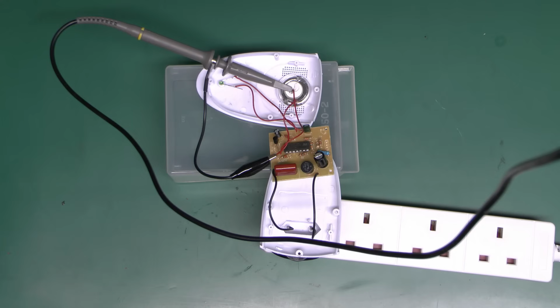Now here's the dubious test arrangement. So mains voltage is in here, circuit board there, and then I've got the probe here connected to the centre of the piezo transducer, and then the negative is essentially that other connection there, though I've done it on the board because it's just easier than trying to get in there with the actual clip. And this lead goes up to the oscilloscope, which is on the shelf above, so we'll just change that view and have a look at that and see what kind of output we've got.